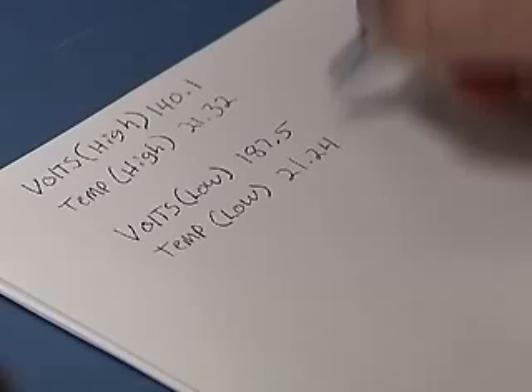The low voltage and high voltage will have a difference between 40 and 55 millivolts on a tip that is functioning properly. This gap will shrink as the sensor tip ages and becomes less sensitive. If it falls outside the 40 to 55 millivolt range, it is time to replace the tip.